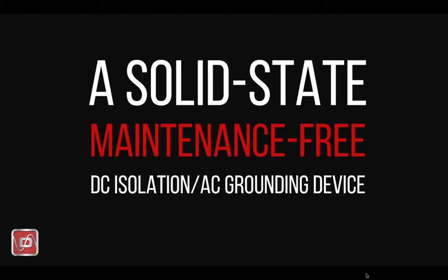Well, we should start at the beginning with the most obvious question. Why do I need a decoupler from Dairyland? We can help with that. First, let's recap what a decoupler is. A decoupler is a solid-state product used for simultaneous DC isolation and AC grounding.